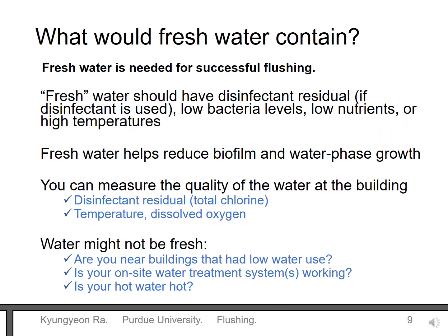The next question is: how do we know if the water entering the building is fresh? After the water is disinfected, fresh water should have some level of chemical disinfectant, normally chlorine. The water should also have low bacteria levels. To find out for yourself if the water is fresh, we recommend a few water tests before and while you are flushing. Consider testing for the chemical disinfectant using an inexpensive digital device. This might be chlorine, and building owners should ask what chemical is in their water. Testing for water temperature is also a good idea. By testing these simple parameters, building owners can determine if the water entering the building is fresh and old water has been flushed out of the building.